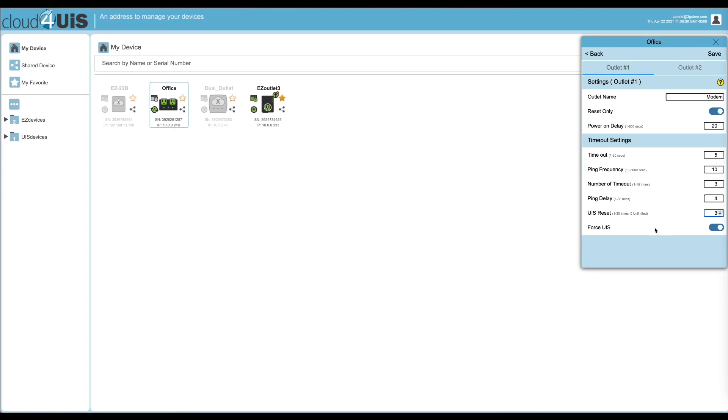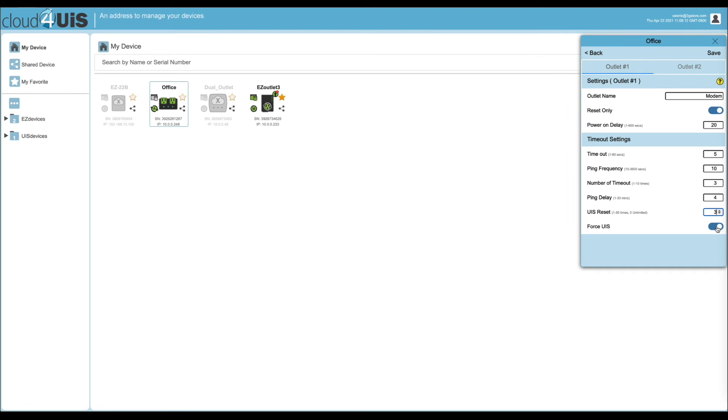UIS reset refers to the number of times the switch will continue to reset if after the first attempt, the connection has not been established. If this is at a remote location, you might consider increasing this value. Lastly, we have the force UIS reset option. This helps if the switch loses power. When it boots up, it will follow the same power on delays to the outlets to ensure your equipment boots up properly.